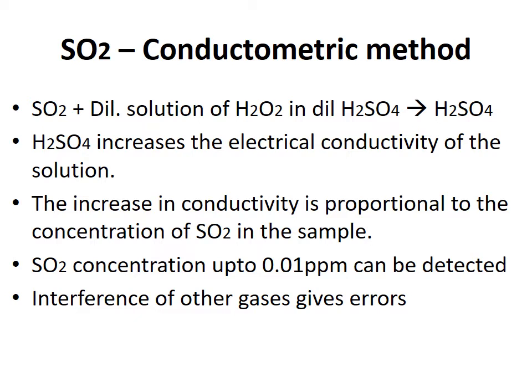The next method for SO₂ analysis is the conductometric method. The sampled air containing sulfur dioxide is passed through a dilute solution of hydrogen peroxide in dilute sulfuric acid. The SO₂ is oxidized to H₂SO₄, thereby increasing the electrical conductivity of the solution. The increase in conductivity is proportional to the SO₂ concentration, and as low as 0.01 ppm can be detected. However, this method suffers from a wide variety of interferences due to other gases, which can introduce error.